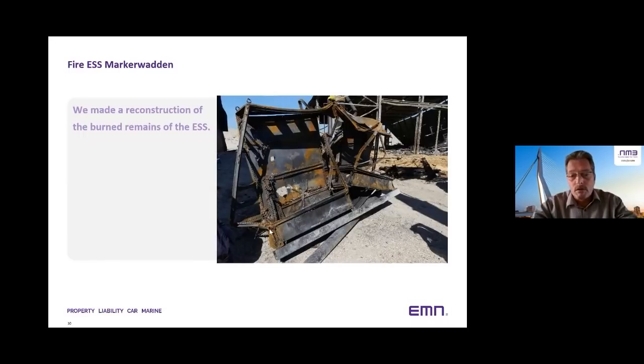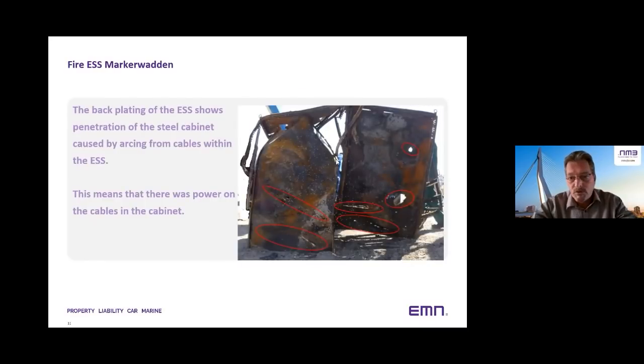We found a lot of melted and short-circuited, burned wires that were hardened and left arcing on the back plate of the cabinet. You can see the red ellipses on the back plate showing where the steel plating was penetrated, and that penetration was caused by arcing from the cables.